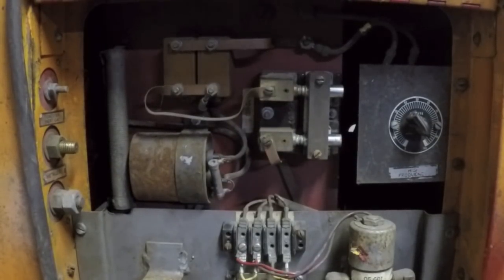So you go to that transformer primary, and when that contactor closes, you better have 120 volts there. If you do, I'd disconnect one of the wires to the primary of that transformer and measure the primary winding. If you have infinite resistance, it means your primary is open on that transformer, and well, you get a big problem because you get a bad transformer.